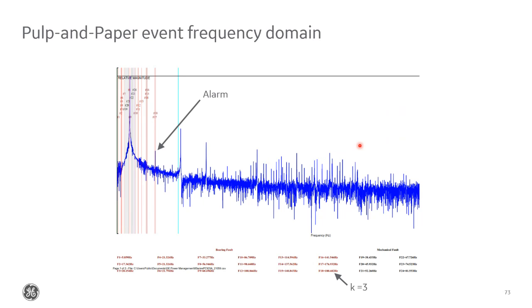And this is the FFT screenshot from that same application. We can see at a specific frequency that there was a spike, and this is what we alarmed on for a bearing failure.